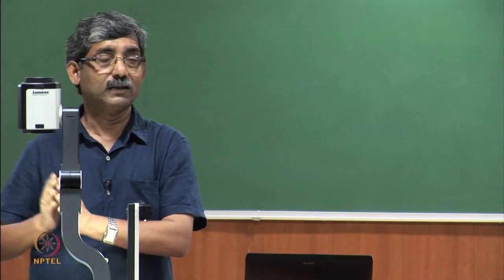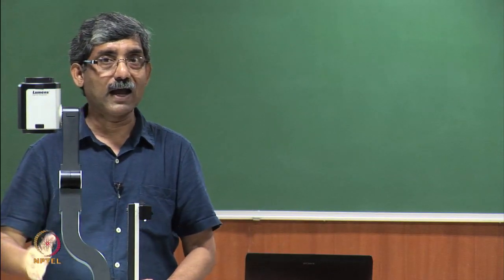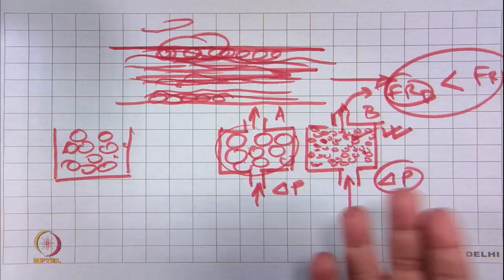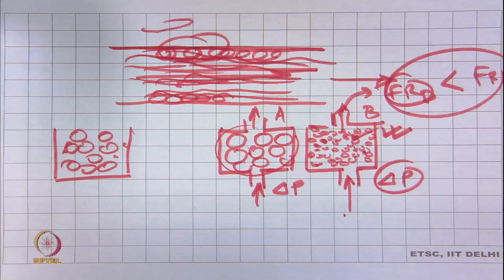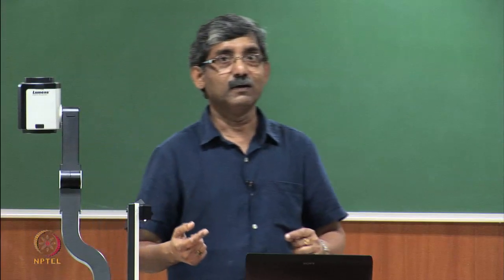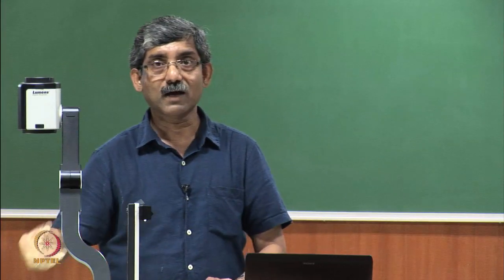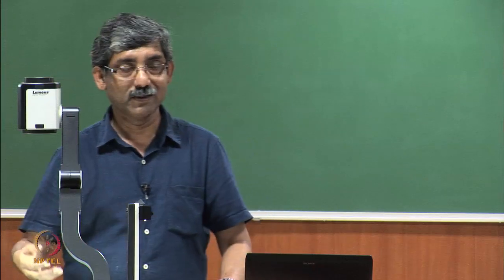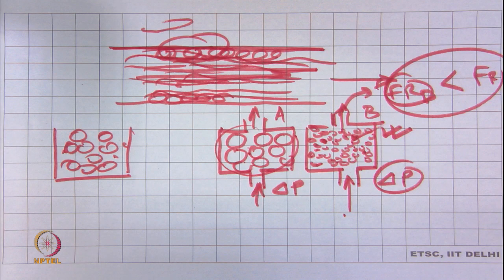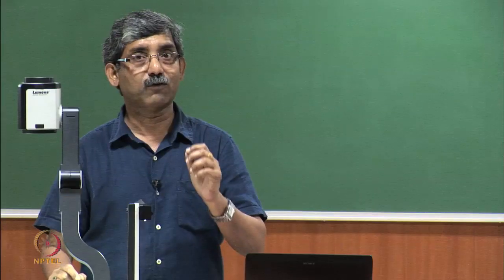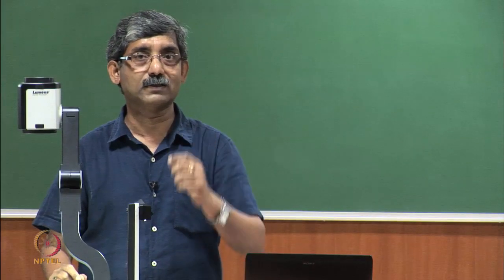We are telling that A has a higher surface area than B, and that way we cannot tell the exact specific surface area. But from a large number of pre-calibrated data, we can calibrate the instrument, and from there we can tell the actual value.